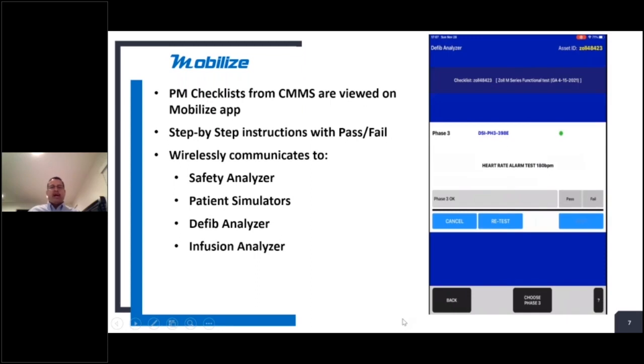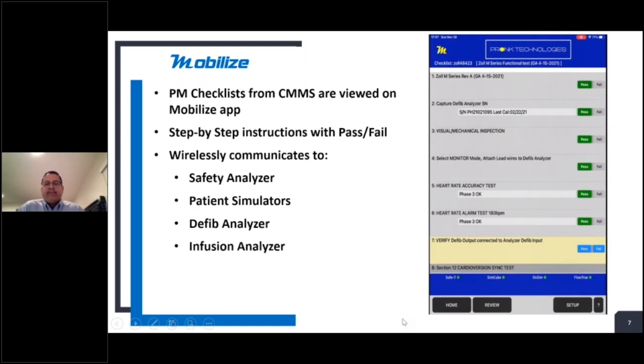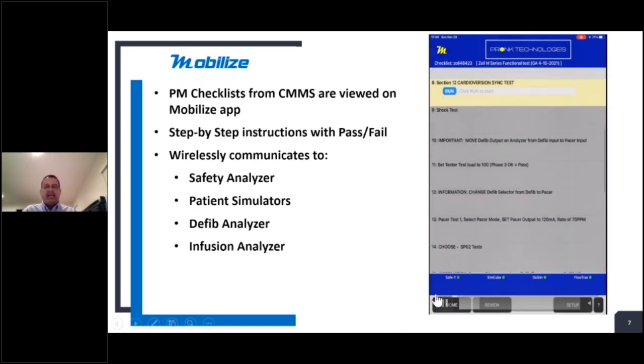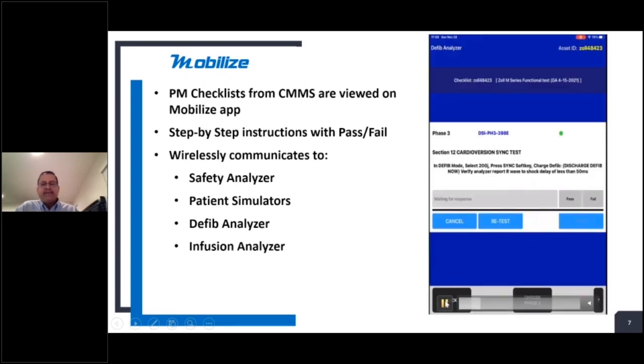And so you're executing the test per the procedure, and you're having the equipment go back and transfer that data back to the application, and you're just working. So all that information is being collected in the background, and it's doing the test. So you can see you can do a wide range of tests. We're going to do a cardioversion sync test here on the Phase 3. It gives the technician instructions on what to set it to, what the test points are, and what the result should be within. And in this area here, once the test is complete and the analyzer has responded back with the result, it would get automatically populated in this field here.